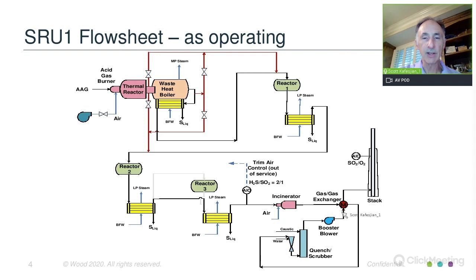Also, this gas exchanger was used to cool the incinerator effluent, and it required a booster blower. And you can see that there's a blower at the back end and at the front end of the process. So it's a difficult pressure balancing, and this incinerator actually has a natural draft burner. So there always needs to be a slight negative pressure here, which normally is okay, but with any minor upsets, this pressure could go positive with serious consequences.